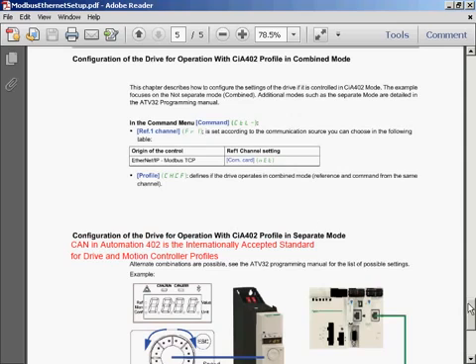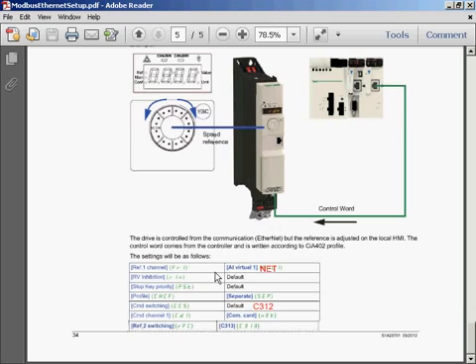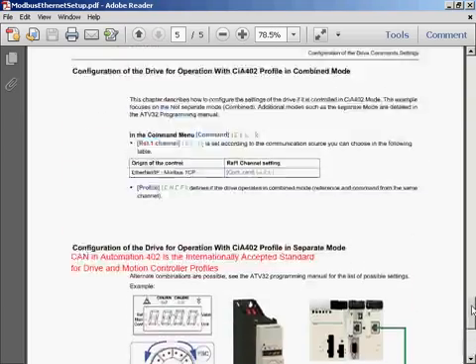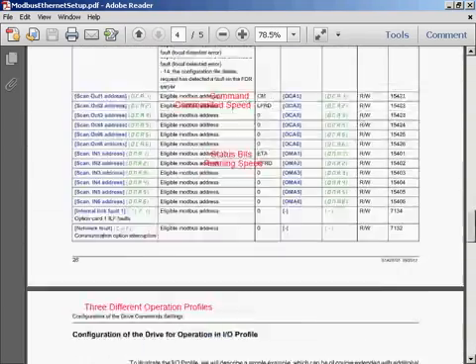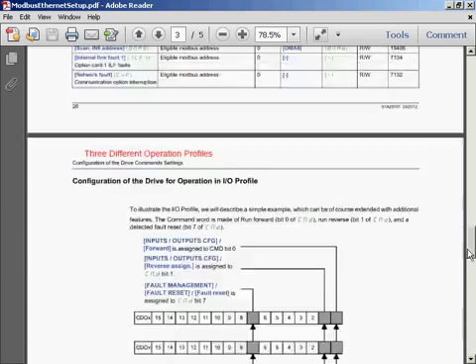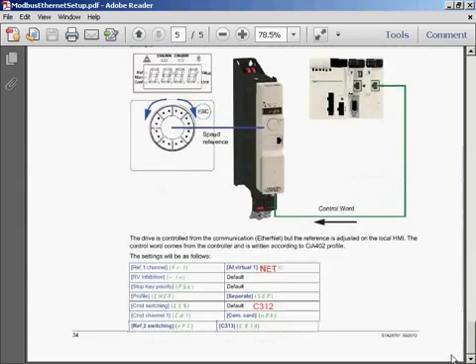I'm going to use the separate mode. So this is what things look like. My first reference channel 1 is set to the comm network. My profile is set to separate. And the command switching is set to C312. This is the twelfth bit of the control word that we talked about here, this control word. Let's scroll back down. And C313 is the thirteenth bit of that control word. So we're going to be able to control this drive from the Ethernet or locally.